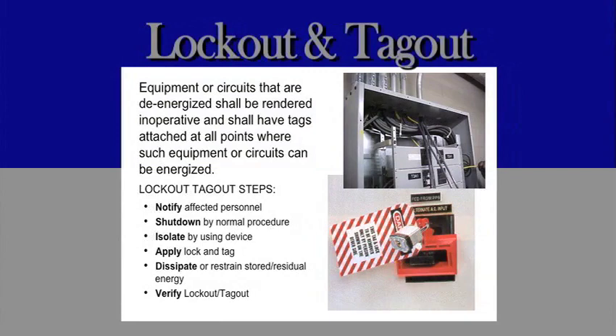Lockout and tagout. Equipment or circuits that are de-energized shall be rendered inoperative and shall have tags attached at all points where such equipment or circuits can be energized. Lockout tagout steps. Notify affected personnel. Shut down by normal procedure. Isolate by using device. Apply lock and tag. Dissipate or restrain stored residual energy. Verify lockout and tagout.